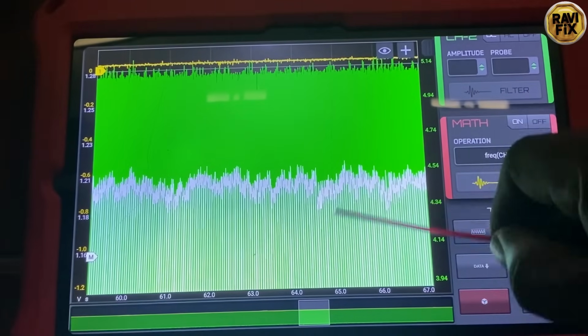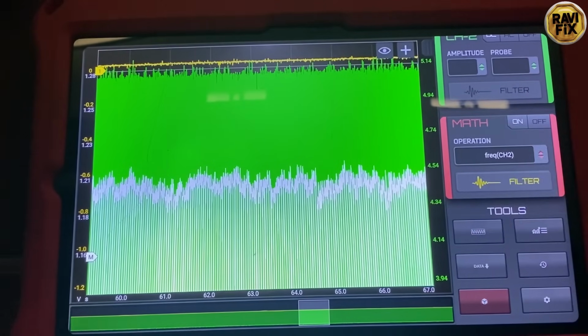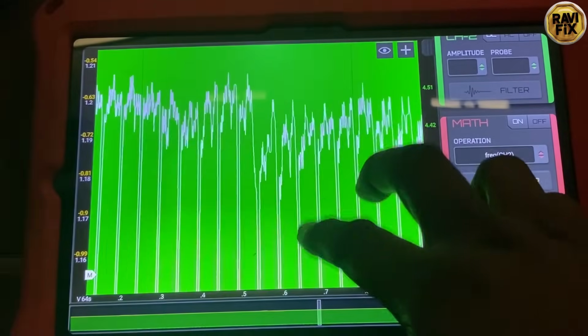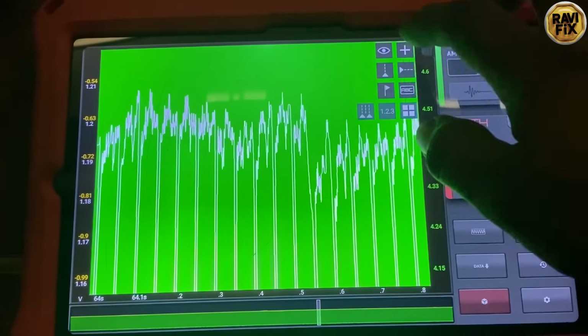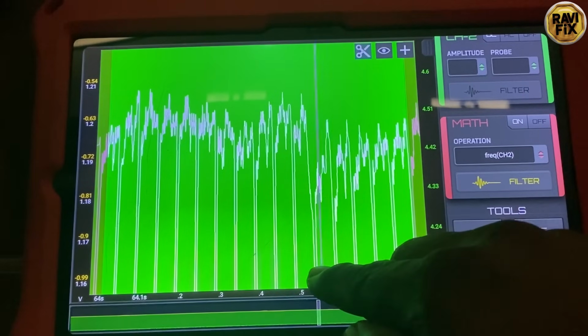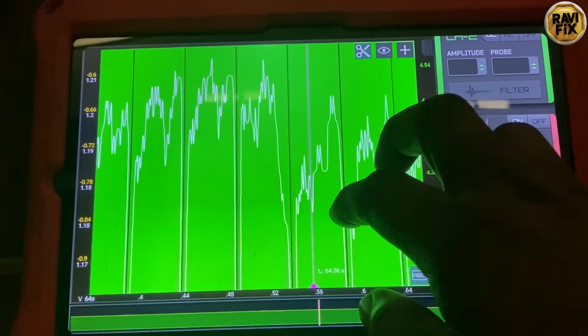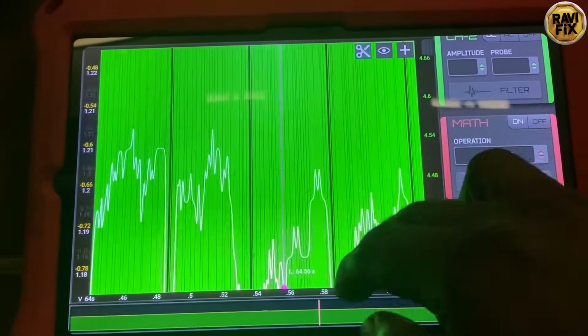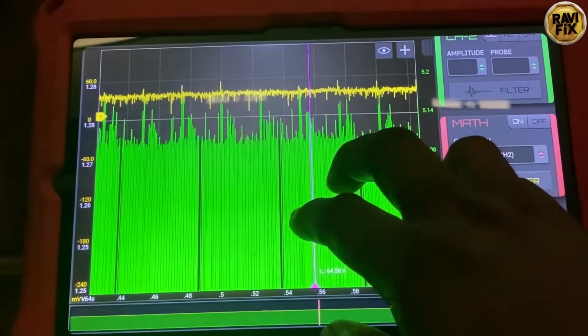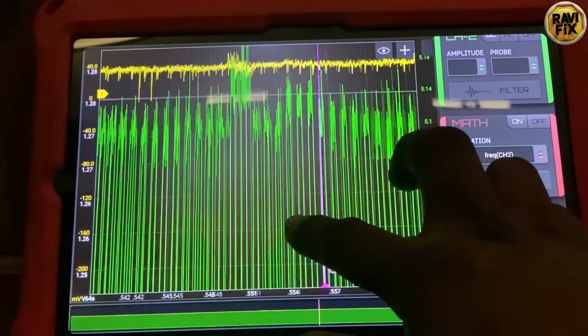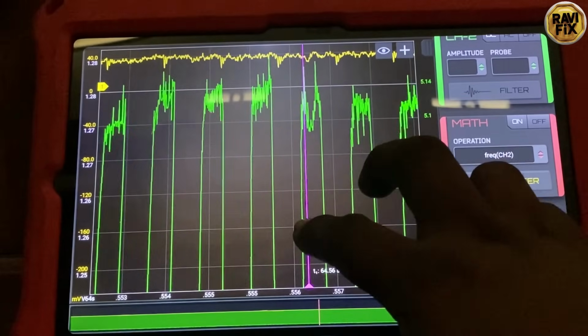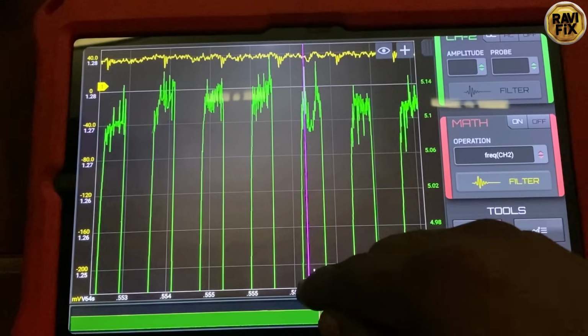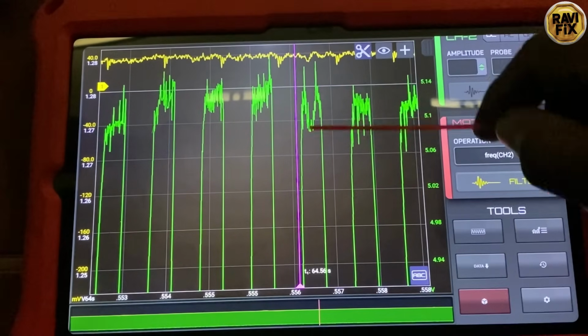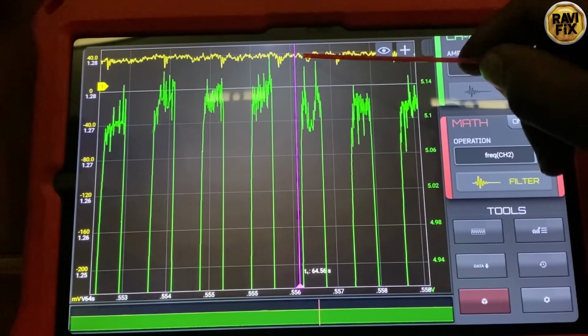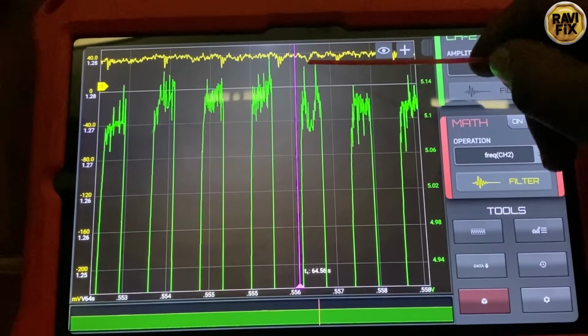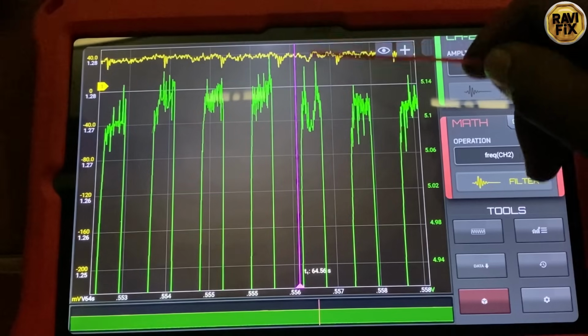Okay, in this area you can see the considerable frequency collapse there. So let's take a closer look, and yeah, you can see this area has a collapse. So I will put a cursor there and align that cursor on that location. So I will move onward to the top, and I will see that glitches appear in the tower close to the cursor. So yeah, do you see that there is a glitch on this tower? Here you can see that glitch. It is perfectly aligned with the yellow trace. That noise comes out from the yellow trace.